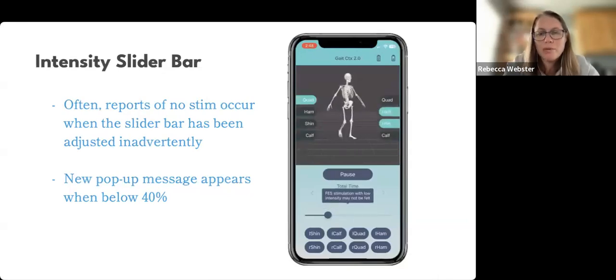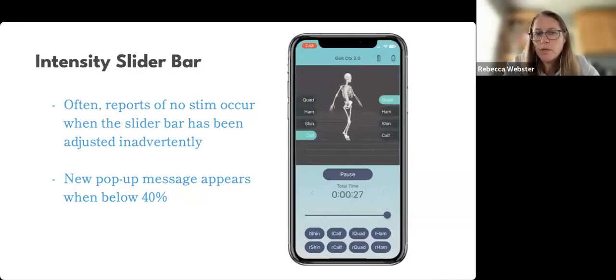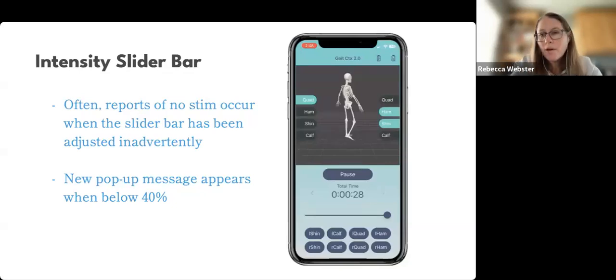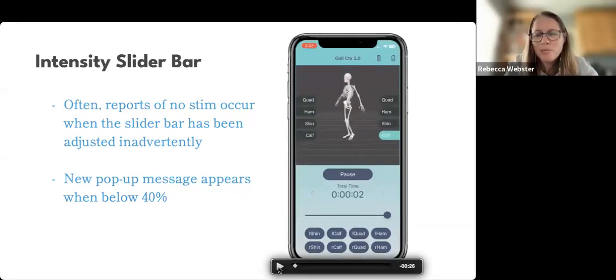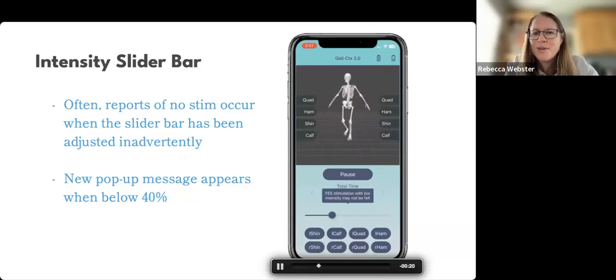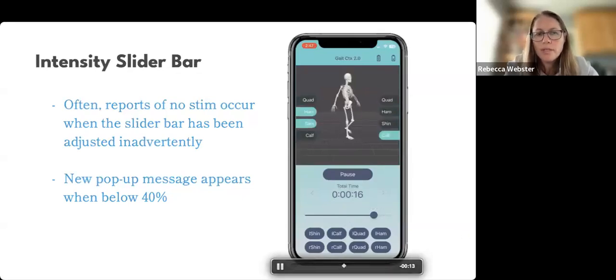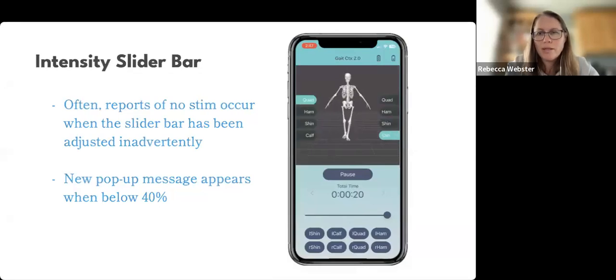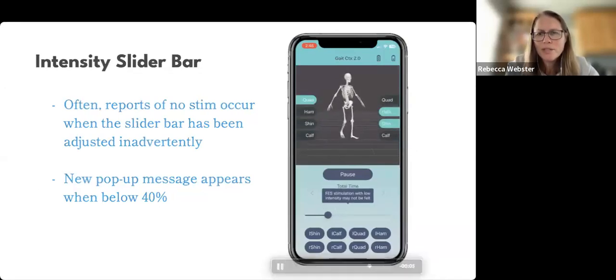And so sometimes we get reports from customers that they don't feel stimulation, or that stimulation isn't working. And what has happened is that slider bar has been moved all the way down to 0 or some lower percentage where it's not felt. So now there is a message that will appear when that slider bar goes down below 40%, just as a reminder that slider bar has been reduced, and you may not feel stimulation at that level. So as you can see it pop up there, FES stimulation with low intensity may not be felt. So just a reminder that at the lower levels, you may not feel stimulation. So another check for you in terms of turning that slider bar down.